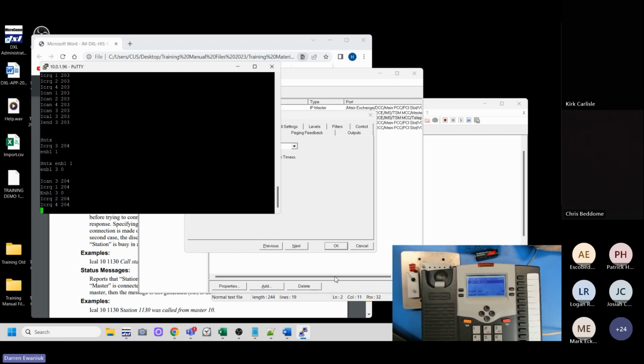So that's one way of forwarding. If you have a fixed scheme, unit calls come into the living unit master. If the living unit master is unstaffed, it goes to a secondary, so maybe a floor control master or maybe a central control. So when the unit master is unstaffed, disable the unit master, and it goes to where it's forwarded to. If the floor master is unstaffed, disable the floor master, and it goes to central control. So that's one way of doing things: you have the fixed secondaries and you just use enable, disable to automatically forward through to its local control.